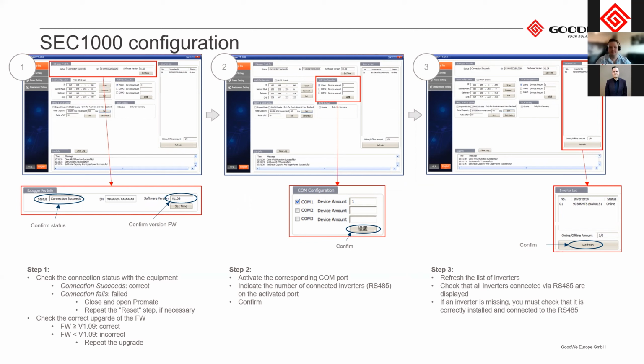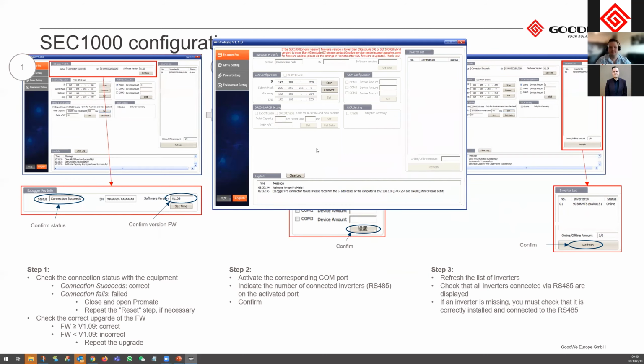So another thing that you will have to do, which is also IT related, which I don't have here, is your computer. You'll have to set your computer also to a static IPv4. So in Promate, you'll see we've got the standard IP address. I can even just pull Promate up so we can see this nicely. So Promate, we've got the standard IP address here. So this is the default IP address of our logger on static mode. So that's the 192.168.1.200. We have to set our computers to the same range as this.